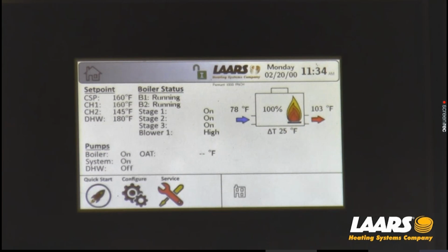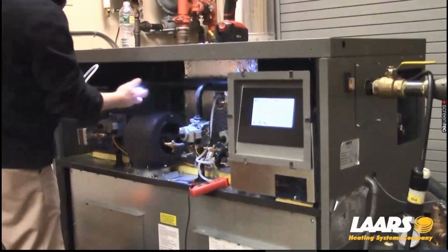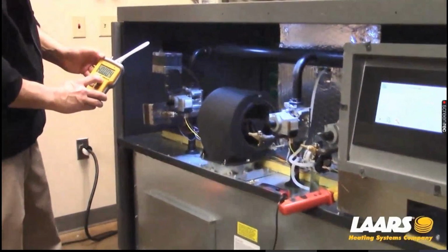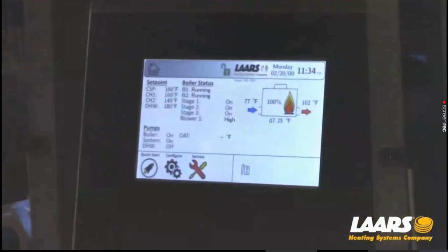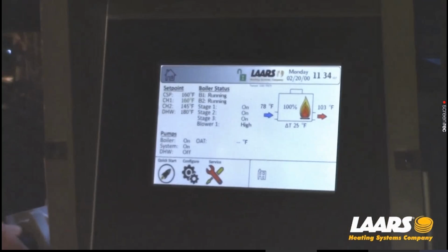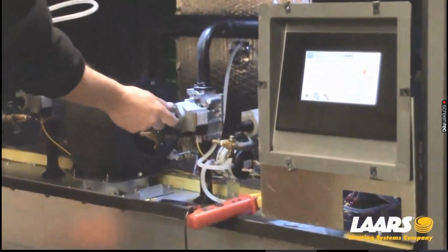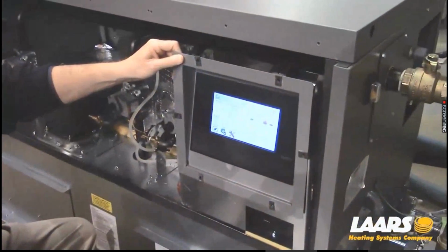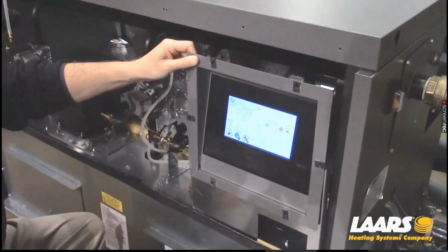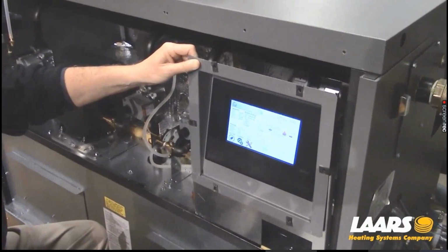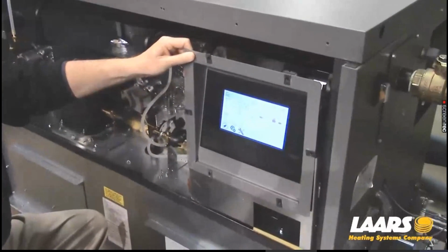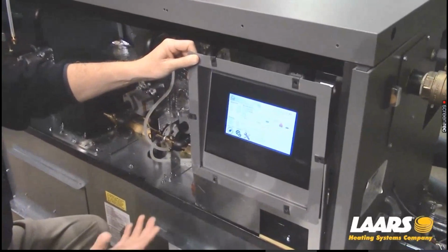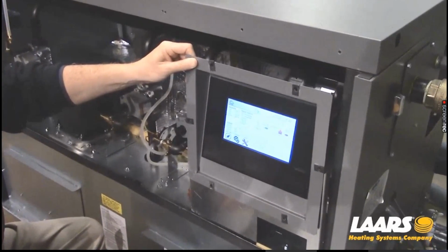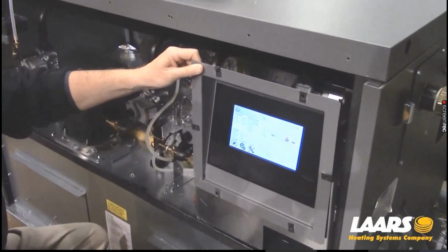However, one thing we have to do first is test the manifold gas pressures. Measuring the manifold pressure is done at each gas valve. We'll shut off all of the valves except for the one that we're testing the manifold pressure at. And there's two ways of turning the valves off. One is by the touchscreen display, which I'll show you first, and then the second way is by manually shutting the gas valves off. Why we typically use the digital display is if you have a larger boiler, greater than a 1 million BTU boiler, it will have two sets of igniters. If we shut it off digitally, it won't lock out that second half of the boiler. If we shut it off manually, it may lock out the second half and you would have to reset it.